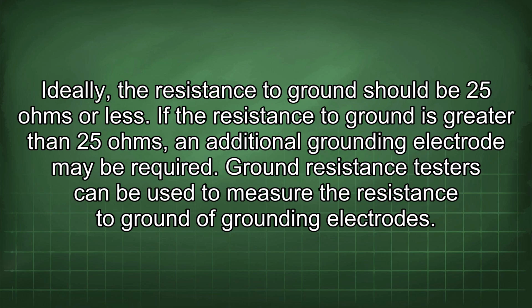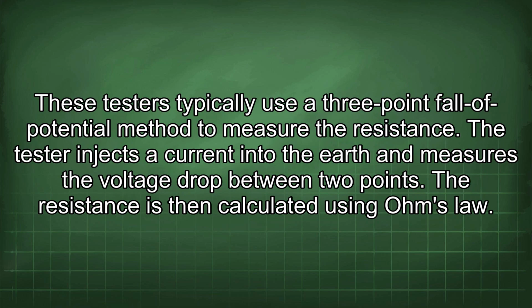Ground resistance testers can be used to measure the resistance to ground of grounding electrodes. These testers typically use a 3-point fall of potential method to measure the resistance. The tester injects a current into the earth and measures the voltage drop between 2 points. The resistance is then calculated using Ohm's law.